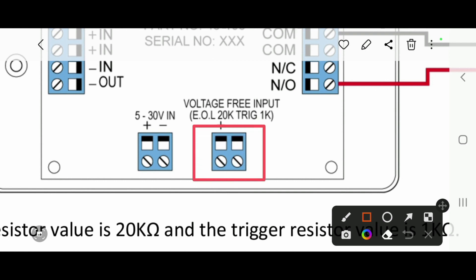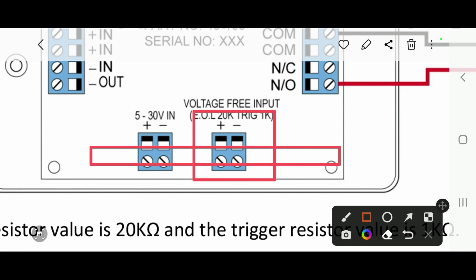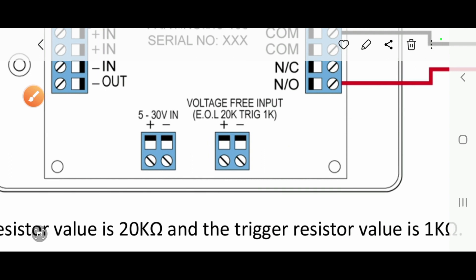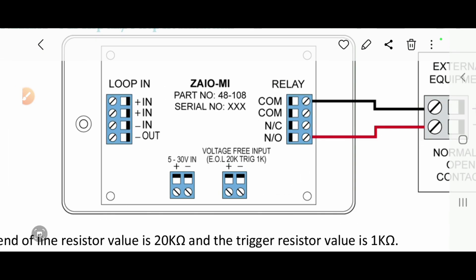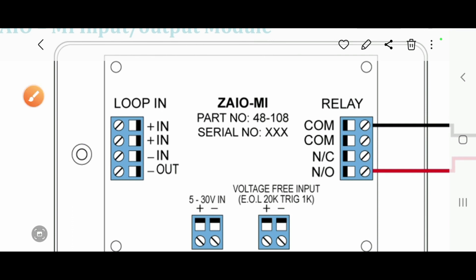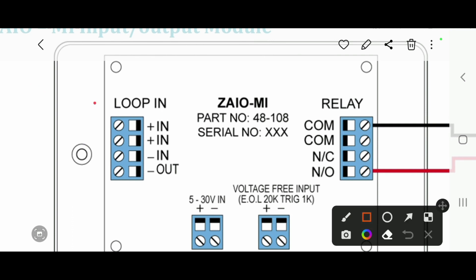This is the end-of-line resistor — plus and minus — and the value is 20K. The end-of-line resistor value is 20K, and the triggering resistor value is 1K. For other panels, these values will vary. This is our module — you can see the loop connections here.